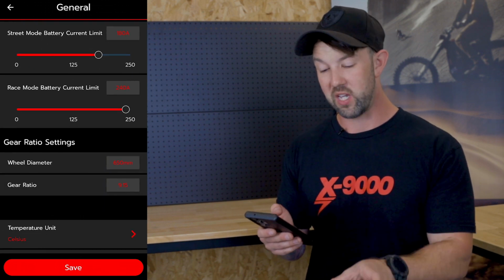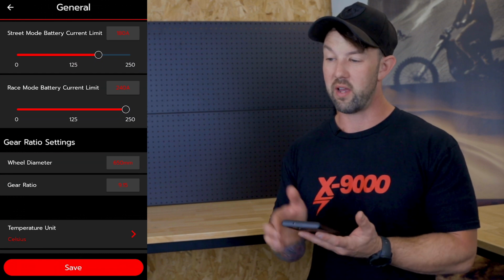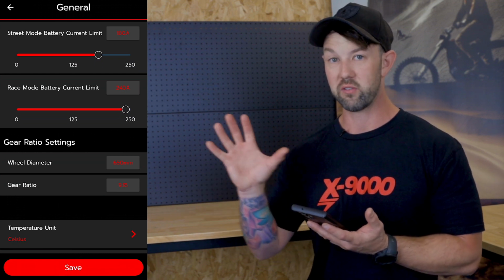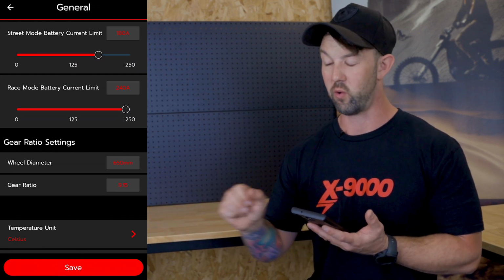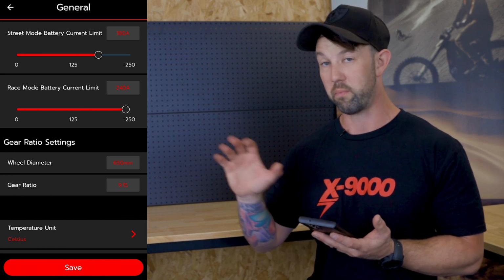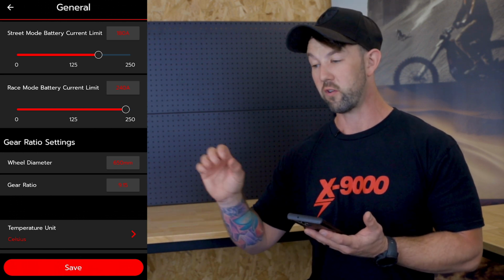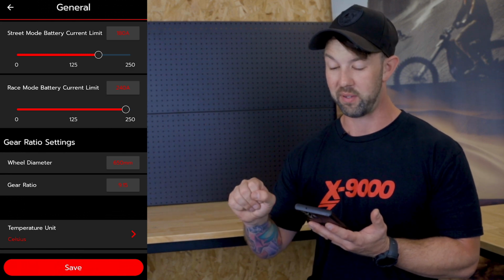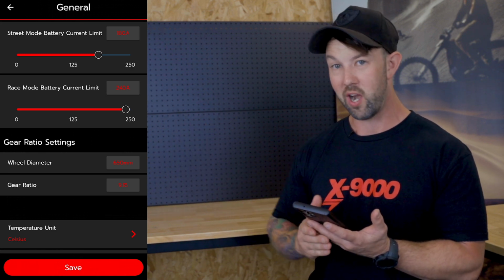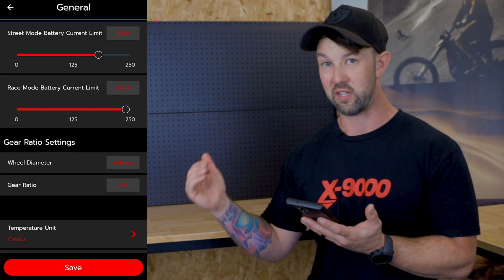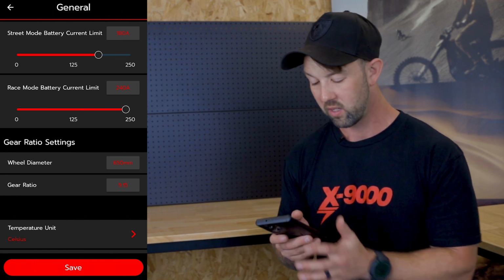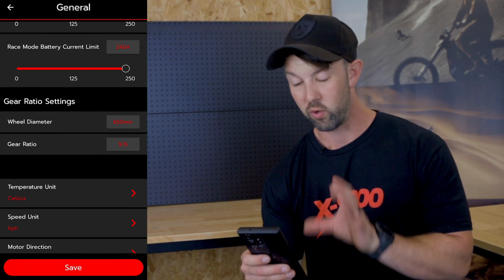You really want to be careful where you set this current, and remember that the controller will generally clamp that current back slower than what the battery will. So if you set this to 240, you could peak at 260 or 270 for a split second before the controller starts clamping that current back. If you're worried about peak limits or overshooting, you need to set this lower than what you'd think you'd need to.